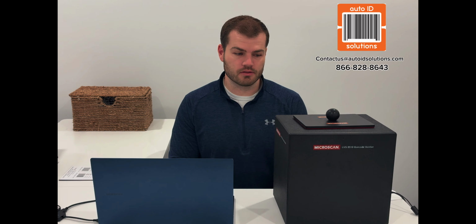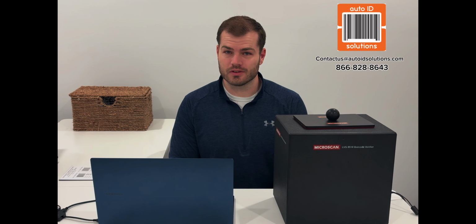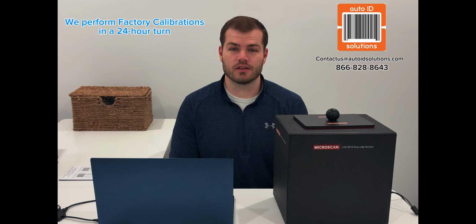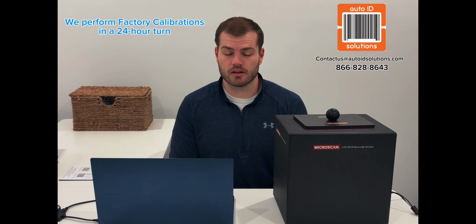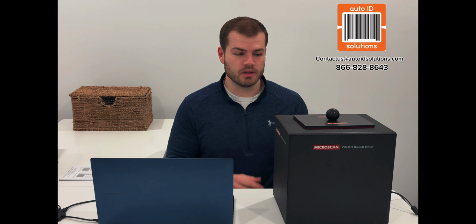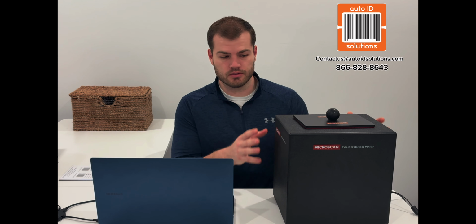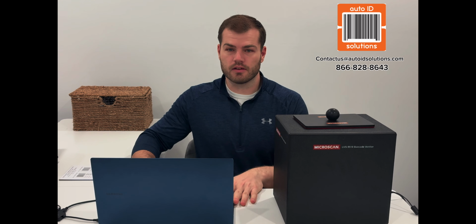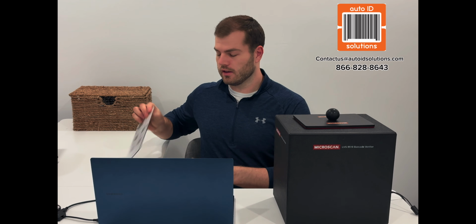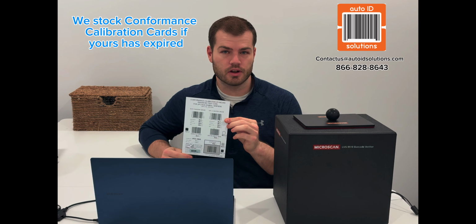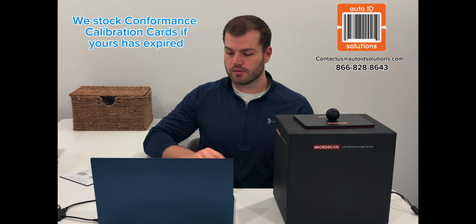We also strongly advise that you factory calibrate your units annually to ensure compliance with ISO standards and receive a certificate of calibration. So to complete the field calibration, you need three things. You need the verifier, you need the software downloaded to a PC, and you need a current conformance calibration card. So next we will go to the software.